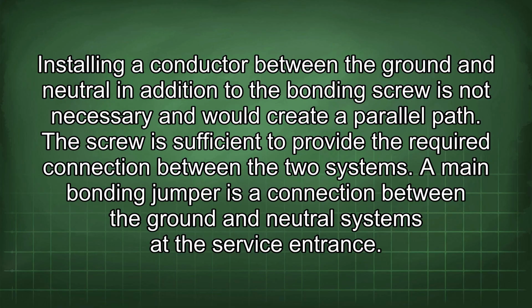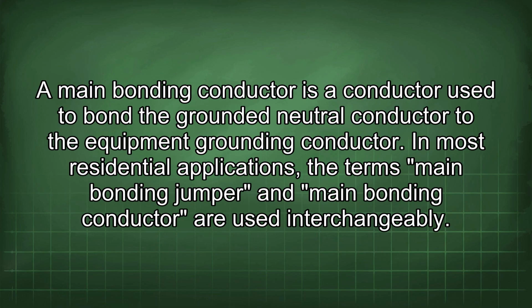A main bonding jumper is a connection between the ground and neutral systems at the service entrance. A main bonding conductor is a conductor used to bond the grounded neutral conductor to the equipment grounding conductor. In most residential applications, the terms main bonding jumper and main bonding conductor are used interchangeably.